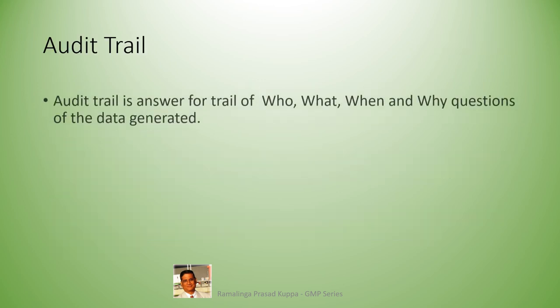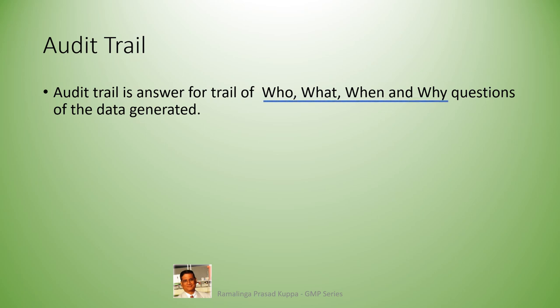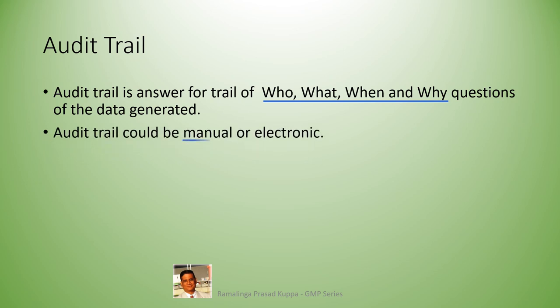Audit trail is the trail of who, what, when, and why questions of data generated. Many get confused with the similar-sounding words trail and trial. A trail is a connection among several objects or items — the connections being who, what, when, and why. If there are justifiable answers to these queries, your data passes the requirements of audit trail. Audit trail could be manual or electronic. Manual operated equipment should have data on log books to answer who, what, when, and why. This is acceptable audit trail compliance.